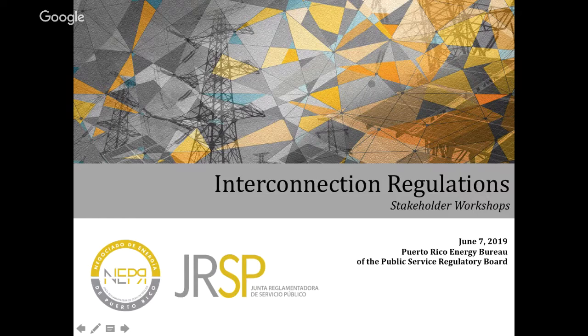Storage systems, for example, we're going to talk about capacity. When one applies for interconnection, one has to state the capacity of the equipment to be interconnected. Now, if I have a photovoltaic system, solar panels limit that system's capacity, because those of us who work with photovoltaic systems look at the back of the equipment, and there's a rating, the ISC, which is the current to short circuit that panel, and then I run the calculation.